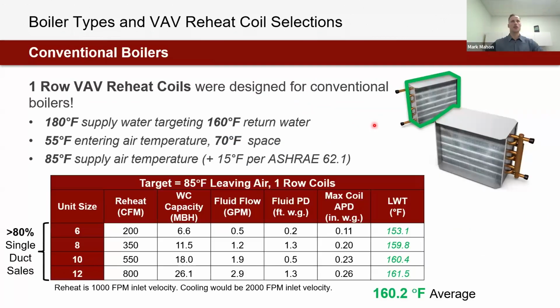So our first view of a kind of fully filled out table here. The big thing to know when we look at a conventional boiler and we look at ASHRAE fundamental design conditions, a one-row VAV reheat coil was designed for a conventional boiler. What we have here is our 6, 8, 10, and 12, all targeting an 85-degree leaving air temperature, which is what ASHRAE would suggest is ideal. We have a one-row coil, and if I take the mass average of these 4 single duct units, our return water temperature is almost bang on 160 degrees.